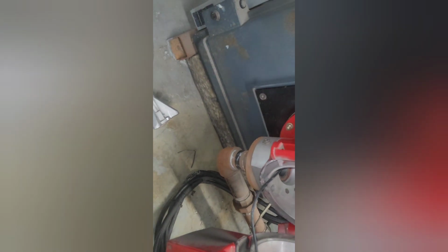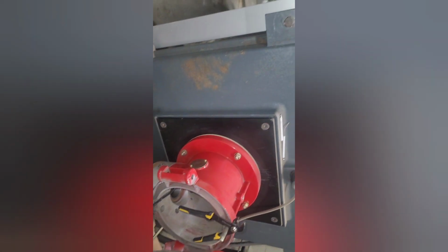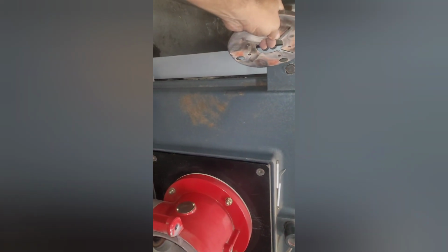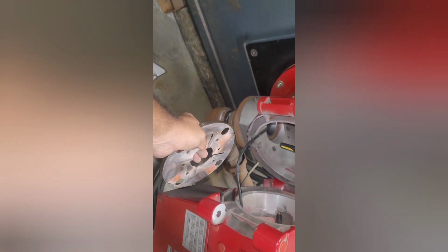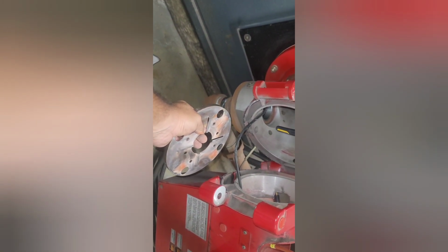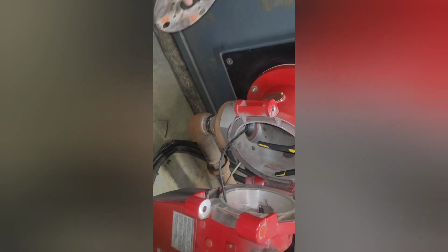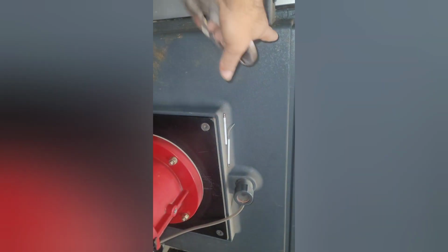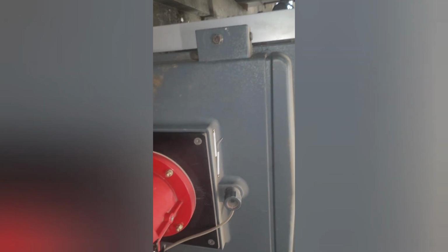I have already cleaned the heat exchanger. To clean the heat exchanger, I have to open up these two bolts and open up the gas line union and the hose, sorry, not this one, those four bolts, and it will open up like a door, and inside we have a heat exchanger.